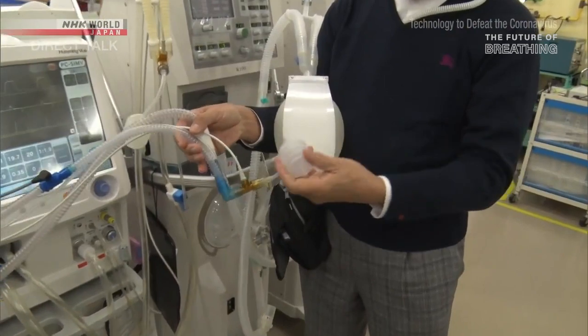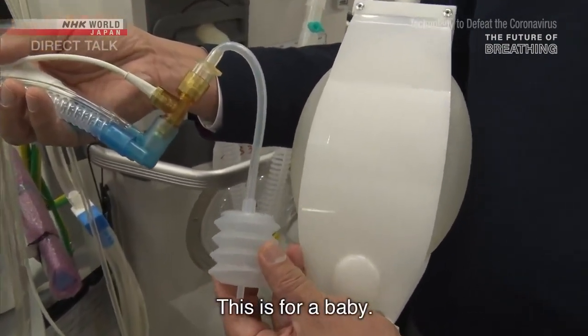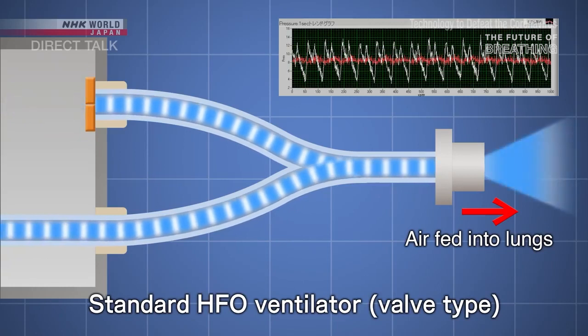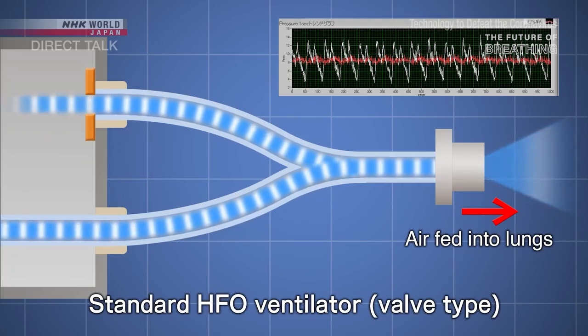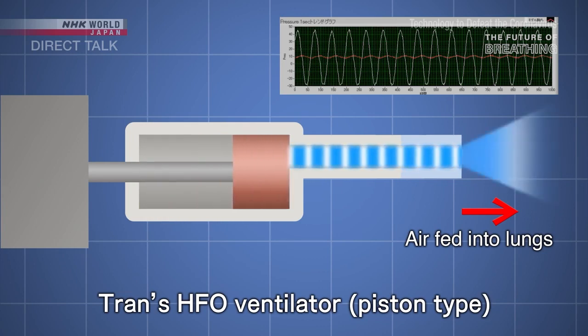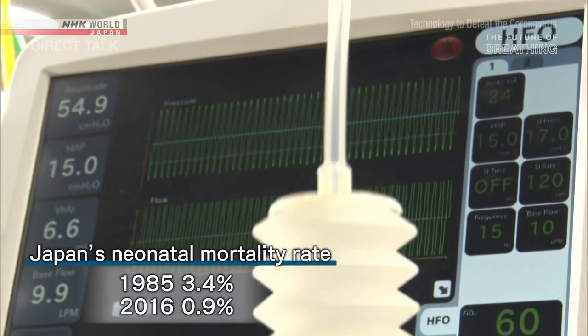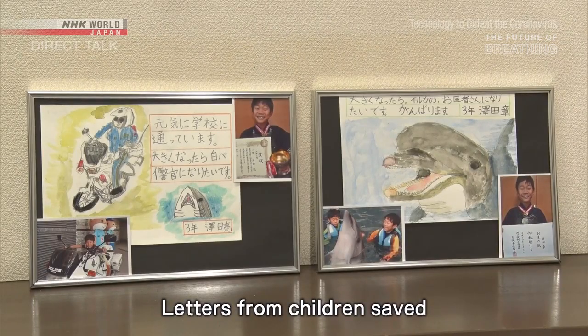The small lungs of a premature baby require different, more precise technology to that of adults, so Tran took a novel approach to developing his neonatal ventilator. Standard high-frequency oscillation ventilators use valves which open and close to feed oxygen into the lungs, but they're not designed to make fine adjustments, so they place a burden on premature lungs. Tran experimented with a piston-type ventilator for precision movement. The tiny amounts of oxygen fed each time, up to a maximum of 900 times per minute, put less pressure on small, underdeveloped lungs. Japan's neonatal mortality rate dropped from 3.4 to 0.9 percent in three decades, now one of the lowest in the world. Tran's ventilator saved many babies' lives.